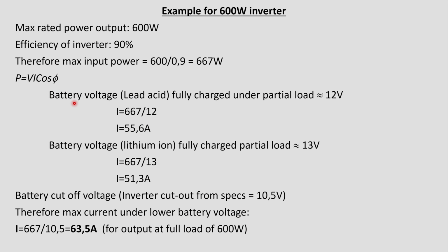All right, so let's look at the battery voltage for lead acid battery. It's 12 volts, although the float voltage is higher. But once I load the unit, it'll be 12 volts or lower. So let's just look at a best case scenario. Say the voltage of the battery is 12 volts and I need to get 667 watts out of that battery. Therefore, my current is going to be 55.6 amps because power is VI cos phi. And let's just assume that the power factor, the cos phi, is 1. So this would be a DC current. So in this case, I need 55.6 amps from the battery if it is a lead acid battery running at 12 volts.